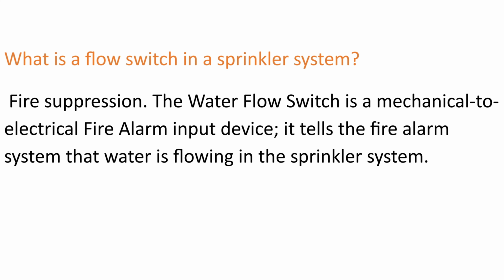What is a flow switch in a sprinkler system? Fire suppression. The water flow switch is a mechanical to electrical fire alarm input device. It tells the fire alarm system that water is flowing in the sprinkler system.